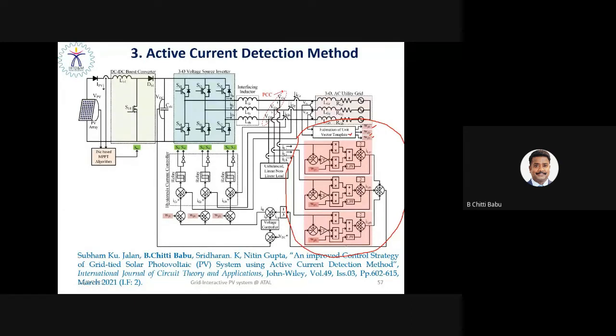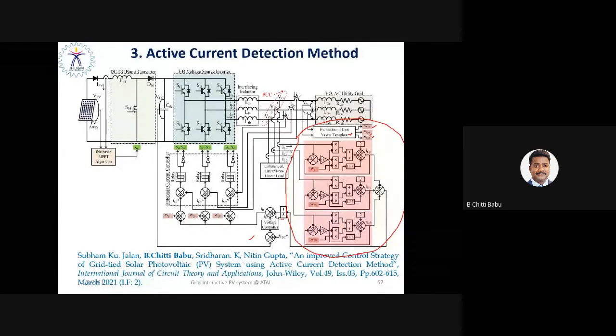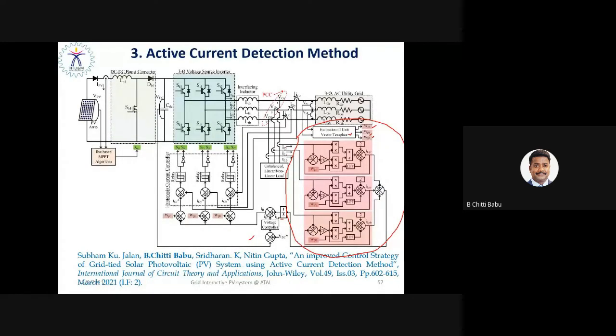Right, the proposed control strategy uses a unit vector template and is computationally efficient, so the control is very easily implemented in the control loop with the help of dSPACE. The DC link voltage is sensed by the sensor. Then the actual DC link voltage is compared with the reference DC link voltage, and the error is given to the PI controller. The PI controller generates the D-axis current component, called the active current component, which is the active reference current. Further, the actual load currents are compared with the reference current. Then we are able to generate the PWM pulses for the inverter. Then the switches work very perfectly, so that we are able to control the integration of solar PV with the utility grid.